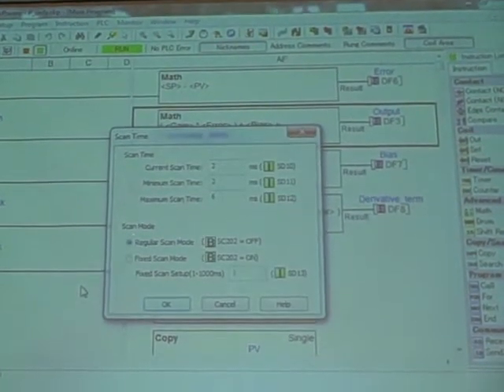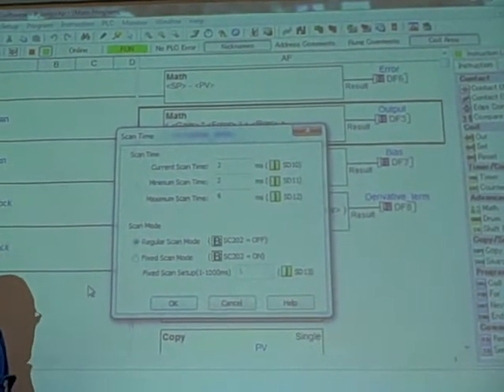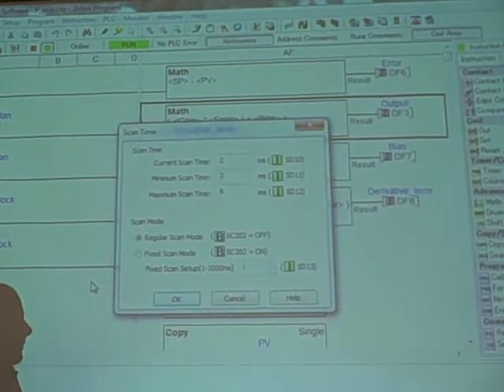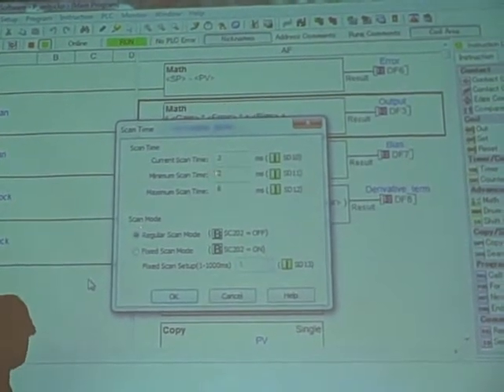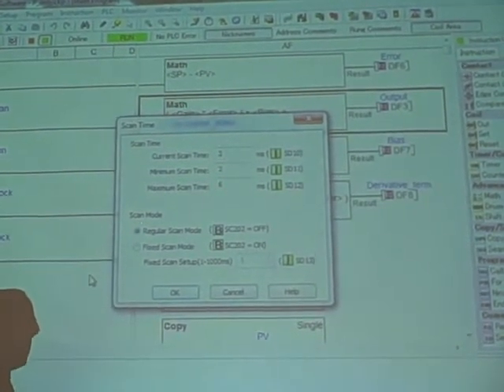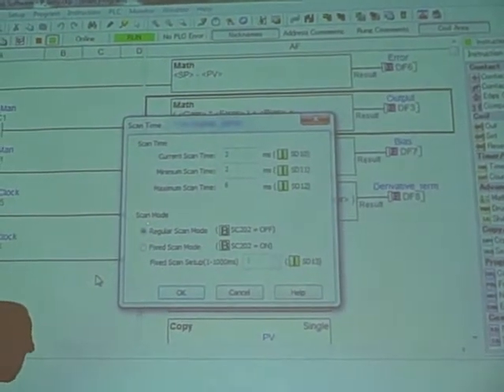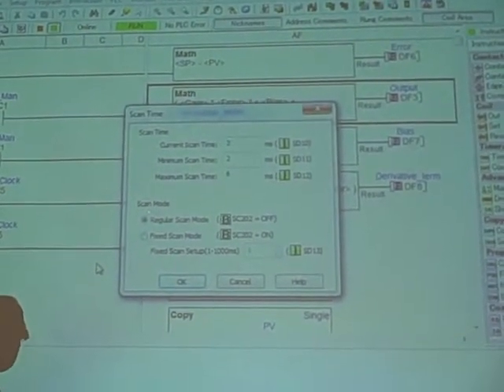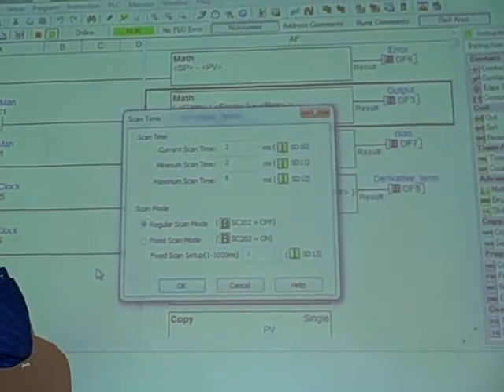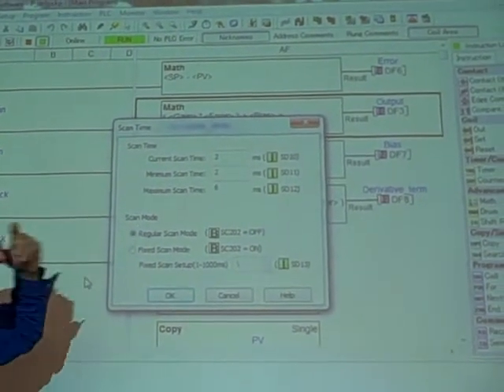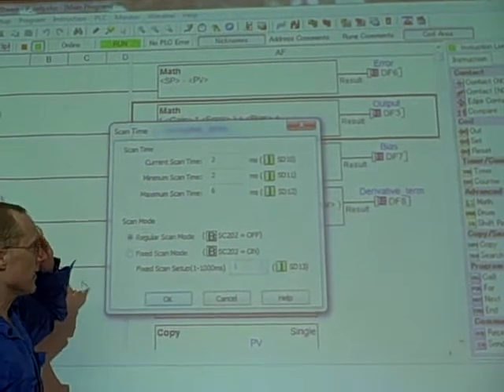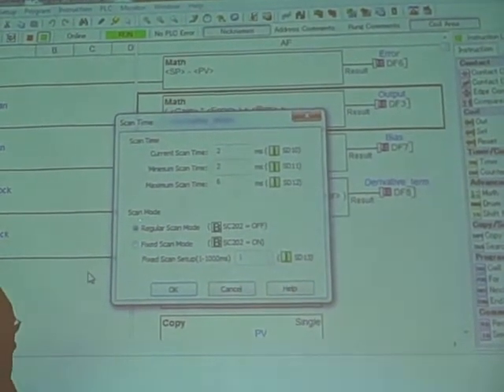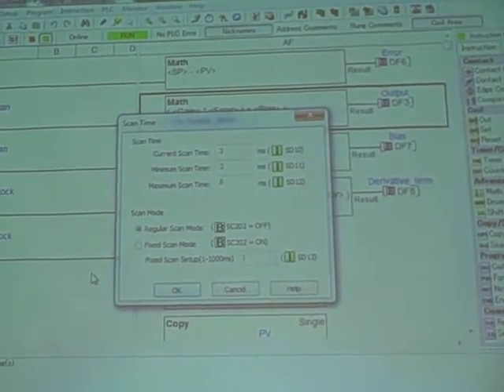Current scan time, 2 milliseconds, 3 milliseconds. That's extremely fast control for a PID controller. The minimum's at 2, maximum's at 6. We can lock in the scan time to some of the values we wish. We can do a fixed scan of this PLC. So what you're looking at here is a very, very fast update time. I'm not even sure the analog ins and outs in this PLC are updating that fast, but just to give you an idea of just how rapidly this program is able to update. It does a pretty good job.